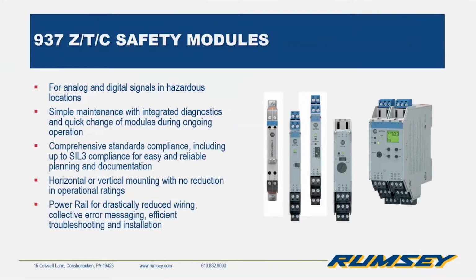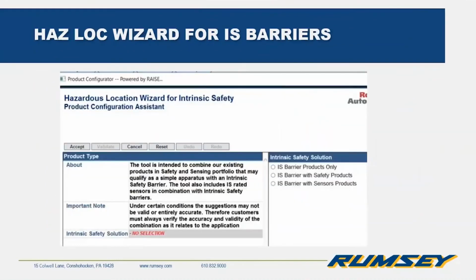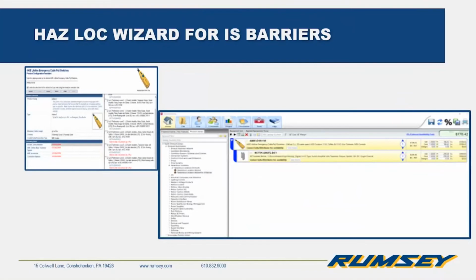And additionally, they can convert or condition signals, just like the previous ones that we showed, the 931. They can perform that same function, but in a hazardous location. And also, these can provide a significant cost savings over traditional methods, which would be a large bolted NEMA 7/9 enclosure or a purge or pressurization kit. And a cool feature that Rockwell has is that when using their ProposalWorks configurator tool, you can come up with an entire intrinsically safe system. So you could find the barrier that you need, as well as the components you need, whether those are safety switches, sensors, or maybe a push button station, and it'll give you a complete bill of material based off of your need.